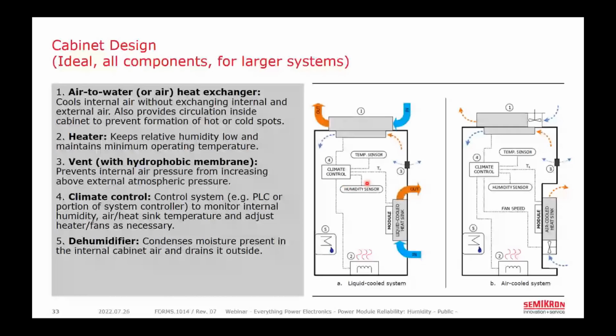And since these cabinets are both closed, we happen to have some air-to-air heat exchangers on the top of the unit to maintain the internal air temperature within the cabinet. And truthfully, these commercially available heat exchanger units generally integrate all of this climate control stuff in. And since they're effectively industrialized air conditioners, they do a good job of regulating humidity as well. Nevertheless, here they are circulating air within the cabinet while we show a separate heater and dehumidifier at the bottom.